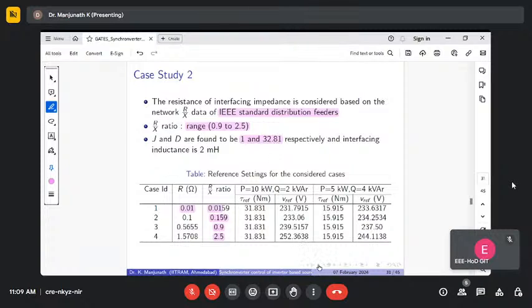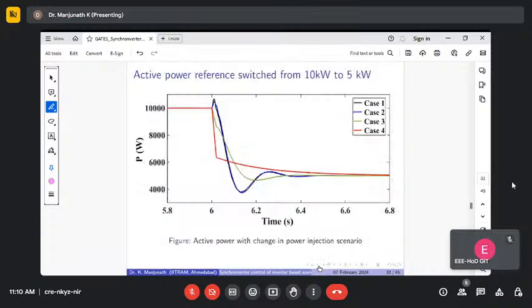Now this is the reference for VREF and torque reference for different switching cases. The first switching is from 10 kilowatt to 5 kilowatt, with reactive power switching from 2 to 4. So essentially we are reducing active power and increasing reactive power in the event of switching. Let us see what is happening.